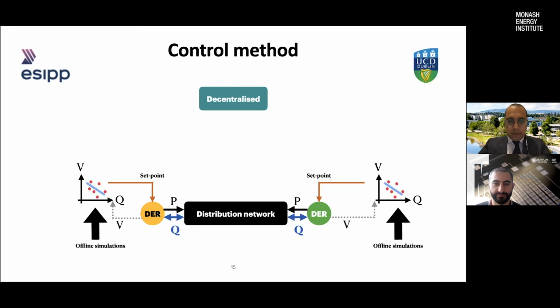You mentioned the volt-var curve gets updated. Is there any predefined time interval to do this update, or is it based on changes to the network loading configuration? Good question. Those volt-var curves are obtained based on some assumptions—network topology, loading of the system, and so on.